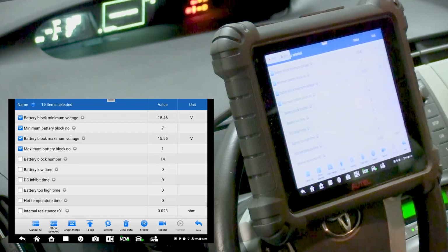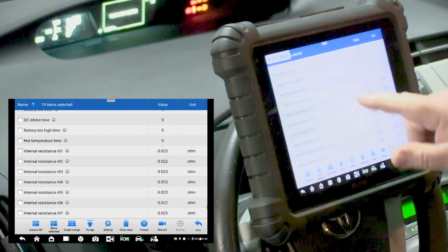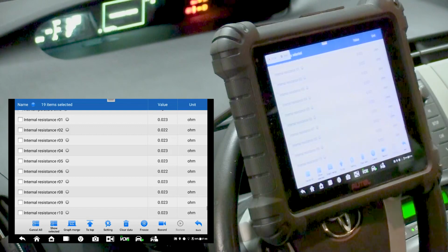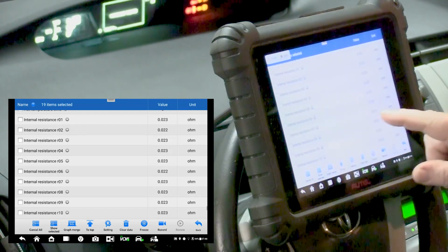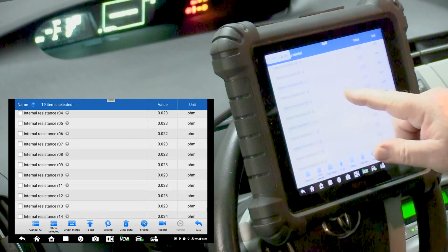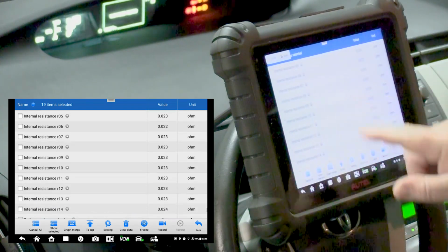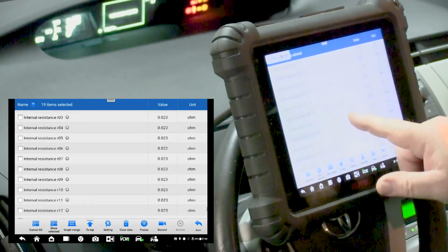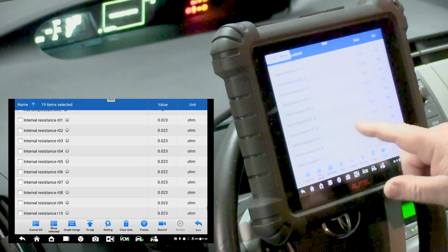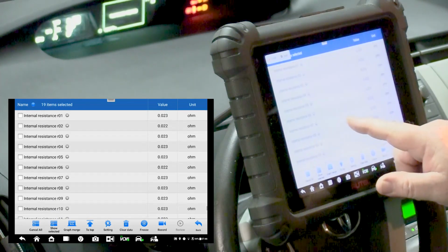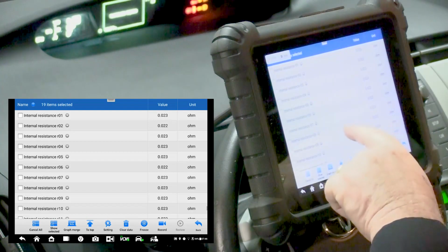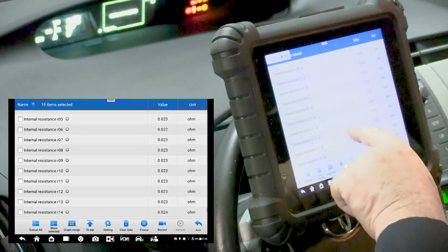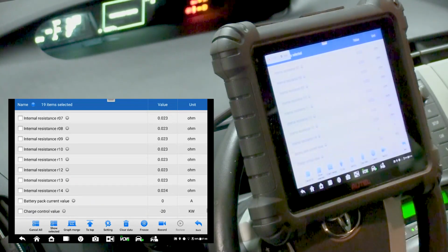All right, now the next thing I'm interested in is internal resistance. These are the internal resistances of those individual blocks, and just like having 14 blocks for voltage, we have 14 specs for resistance. I'm not going to check those off, but we are going to take a quick scan at them. You see they're 0.023, high of 0.024. A good number for this battery pack is around 0.019.